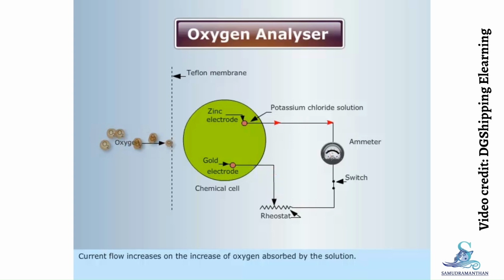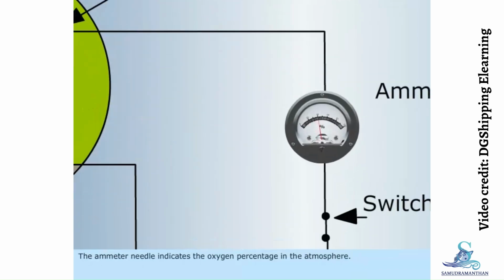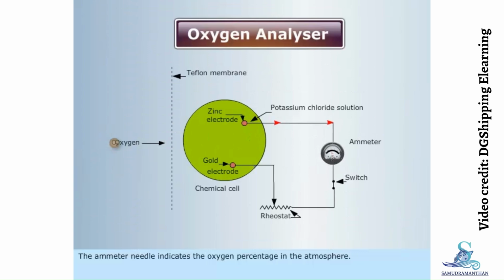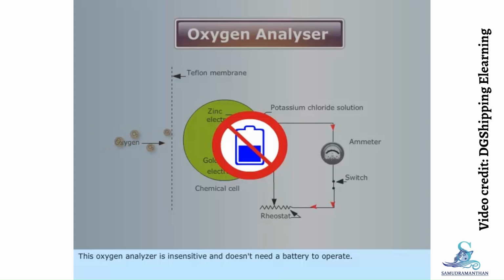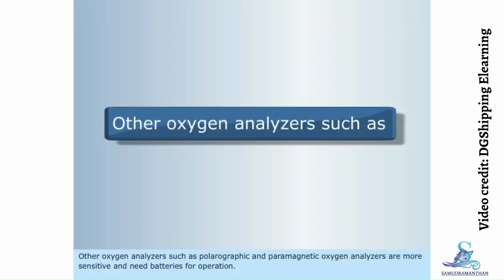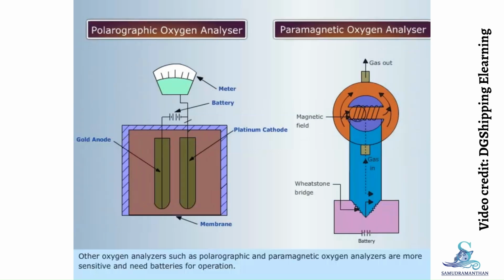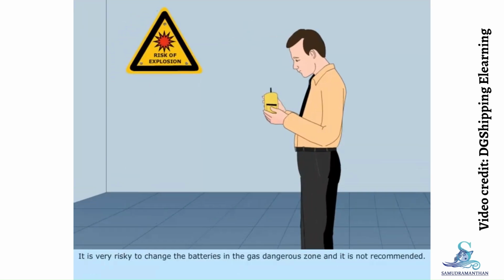Current flow increases on the increase of oxygen absorbed by the solution. The ammeter needle indicates the oxygen percentage in the atmosphere. This oxygen analyzer is insensitive and doesn't need a battery to operate. Other oxygen analyzers, such as polarographic and paramagnetic oxygen analyzers, are more sensitive and need batteries for operation. It is very risky to change the batteries in the gas dangerous zone, and it is not recommended.